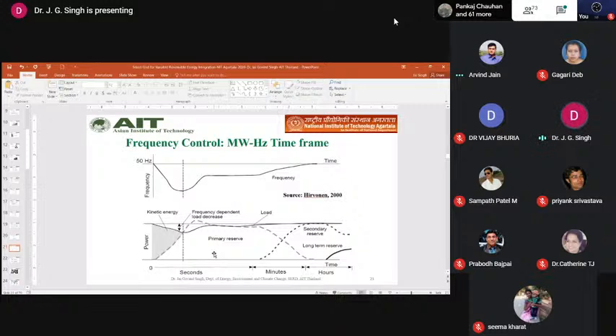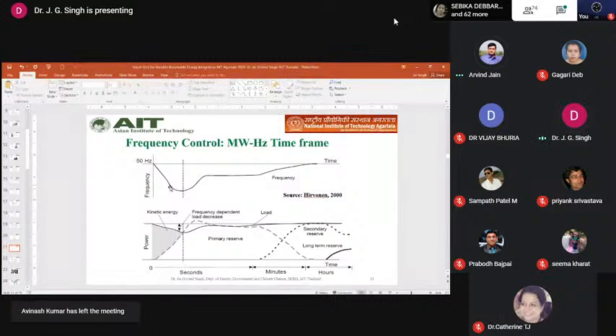In terms of frequency operations, if there's a drop in frequency—because of a large generator outage like solar or wind, reduced power production, or connection of large loads—the frequency starts to drop. At this free-falling point, it can only be stopped by the inertia of the system, which depends on the rotating rotor mass; that releases kinetic energy as power to compensate. But solar has no rotating mass, and wind has very light mass, so this issue creates a problem for renewable integration.